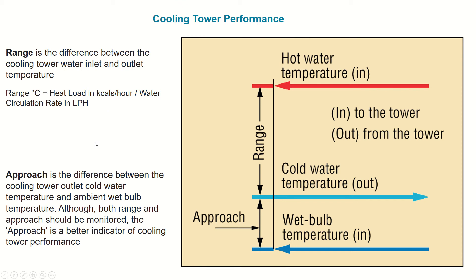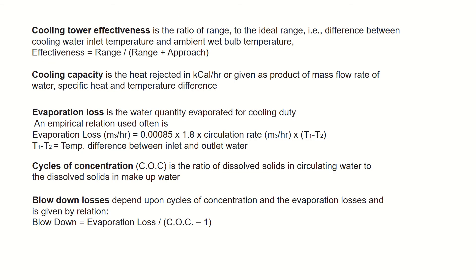Approach is the difference between the cooling tower outlet cold water temperature and the ambient wet bulb temperature. There will always be a difference between the outlet water temperature and the ambient temperature, as a cooling tower cannot achieve the ambient temperature — that is only possible in the case of perfect cooling.